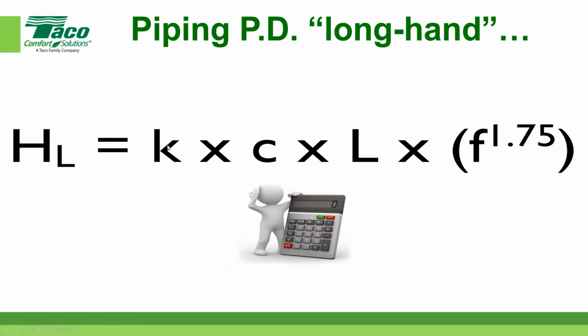This K factor is based on things that we've already talked about. What type of pipe is it? And what size pipe is it, so that we can figure out what the ID is. Now, not only the ID, because we have different types of pipe, we have different roughness factors that are built into this K number. That's why those pieces of software ask you those kinds of questions, okay? That's just a number that's on a lookup table. Then we take that number and multiply it by the C, which stands for your correction factor, which we've already talked about as well. We talked about what the temperature and the mixture of the fluid is.